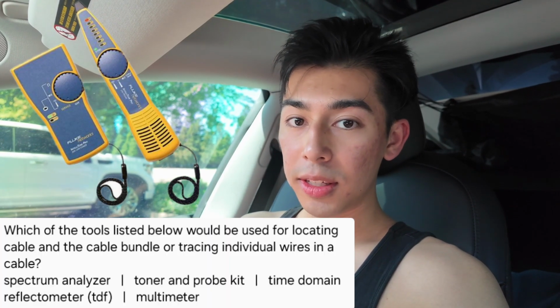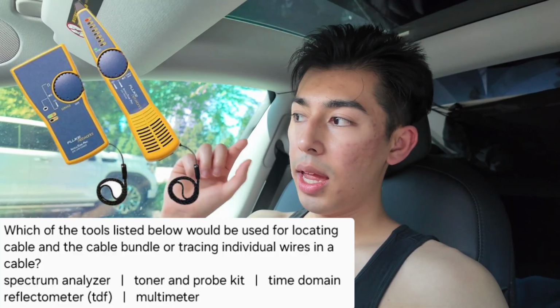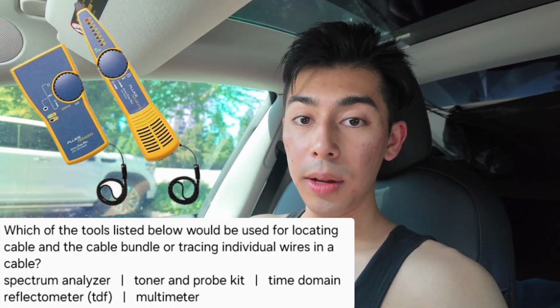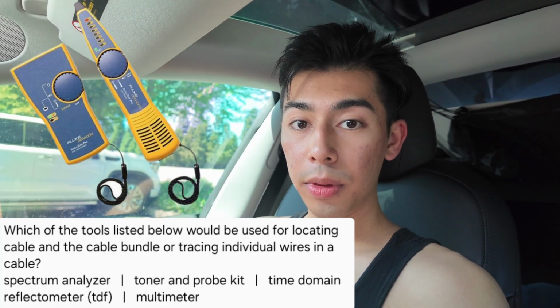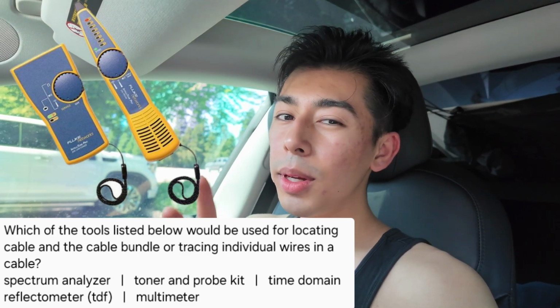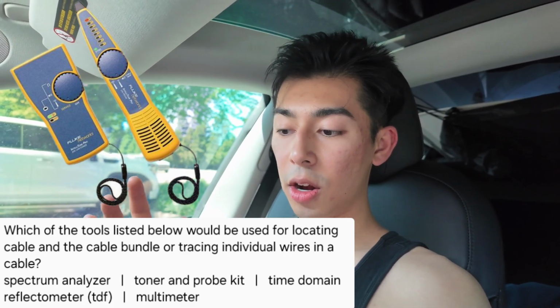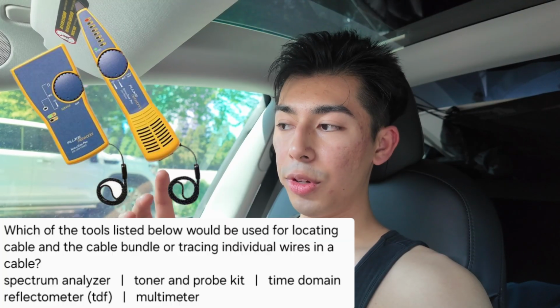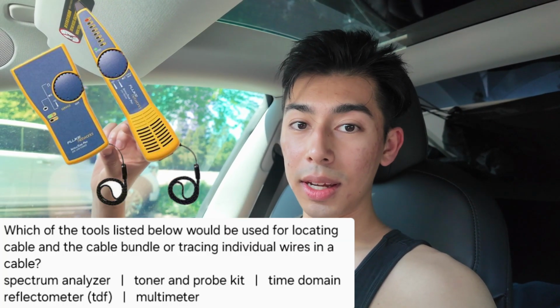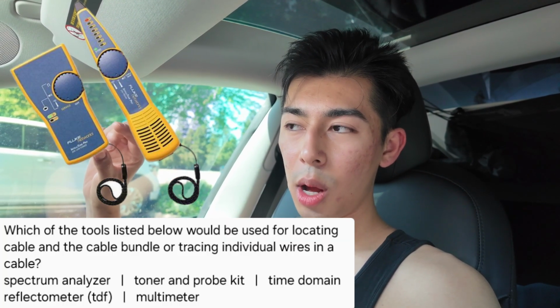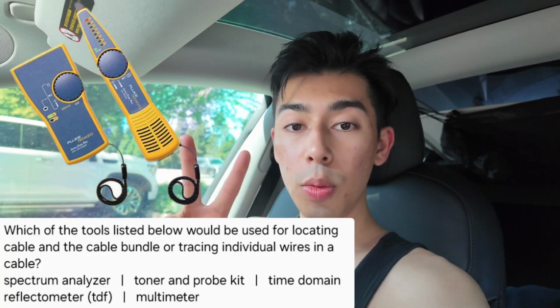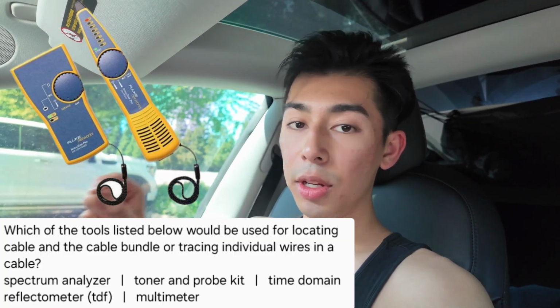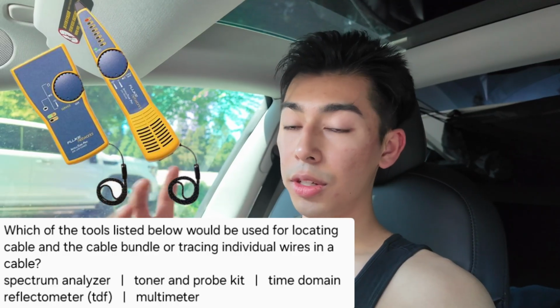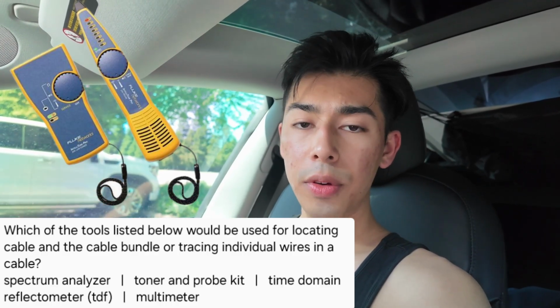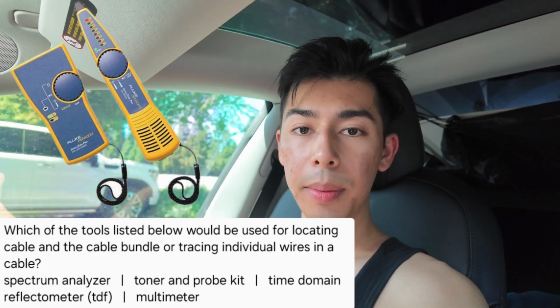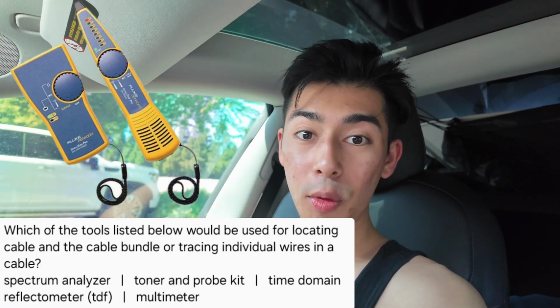Well, for this, it's a tool that you would have on one end and the other end to verify continuity, to verify it's the same wire. So you could use a multimeter for this because it can test continuity, but a multimeter is physically connected with really not long wires. So you have two probes at the very end and you can tap it to a wire and test the continuity, test if it's on the same wire, if there's a lot of resistance. And if there's not, that means it's the same wire.